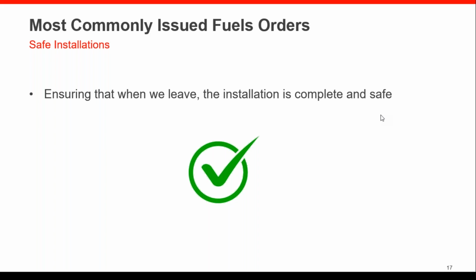And I'll give you an example that we recently were involved in a carbon monoxide incident where exactly that happened: the installation really wasn't completed and really shouldn't have been turned on, but the installer was pressured by the general contractor and/or the building owner. They needed heat or hot water, and they were pressured, and they relented and turned it on, and we had a CO incident. So it is your responsibility to ensure safety when you leave that installation.